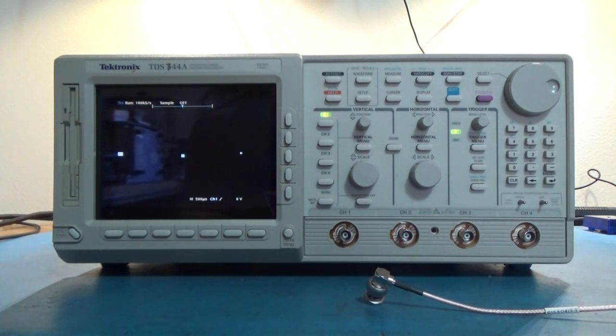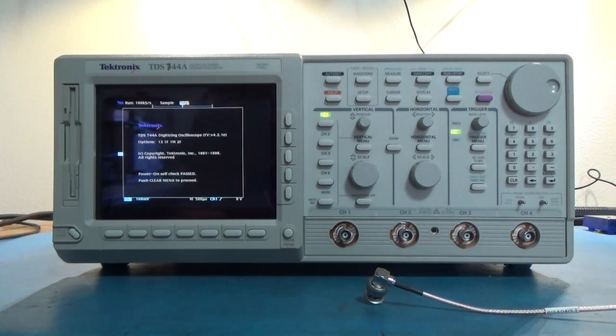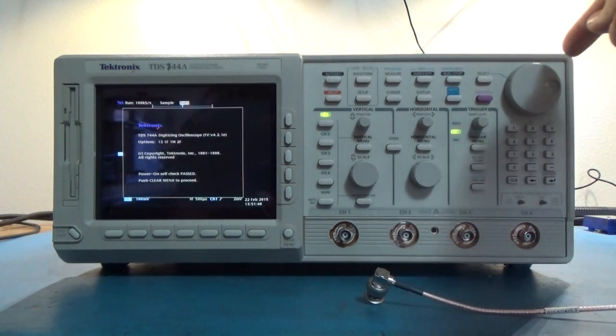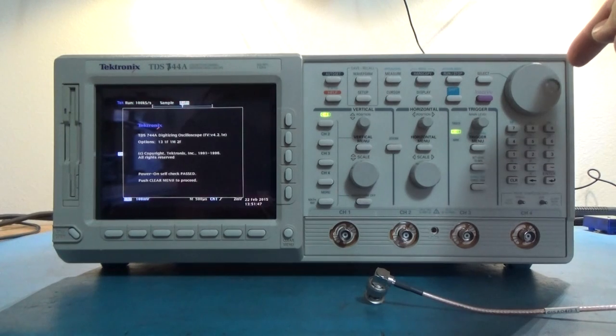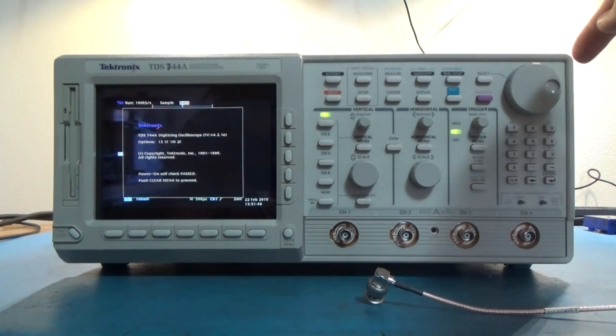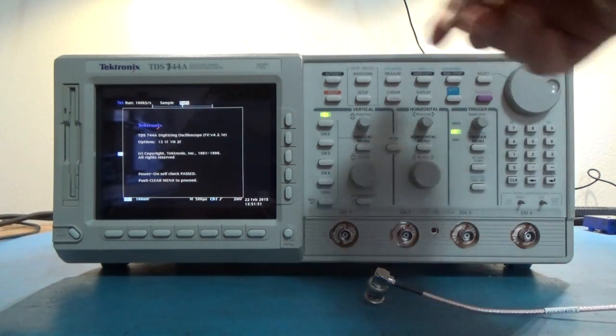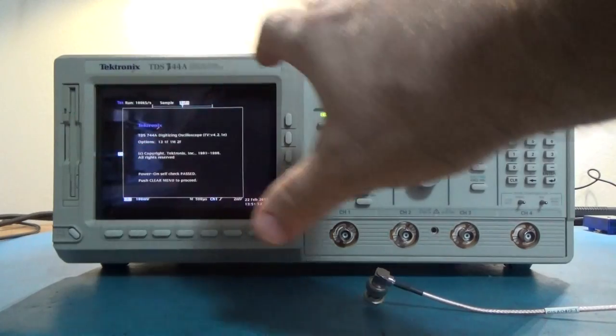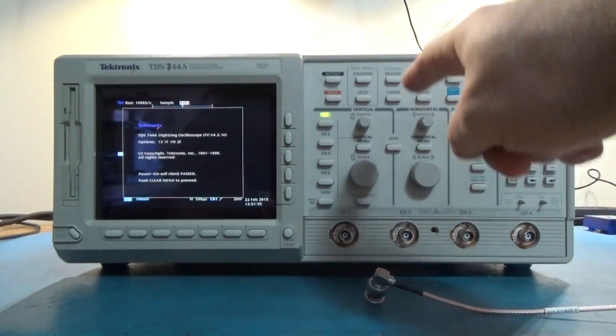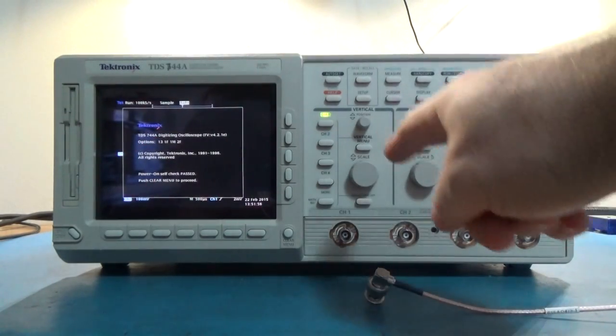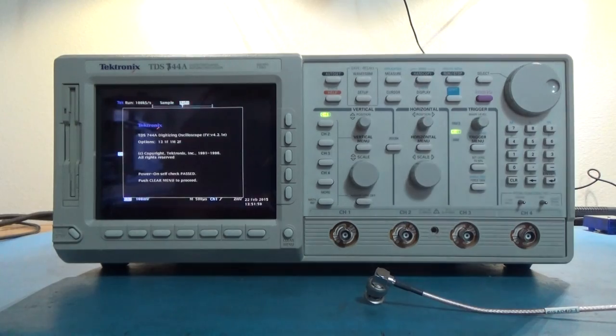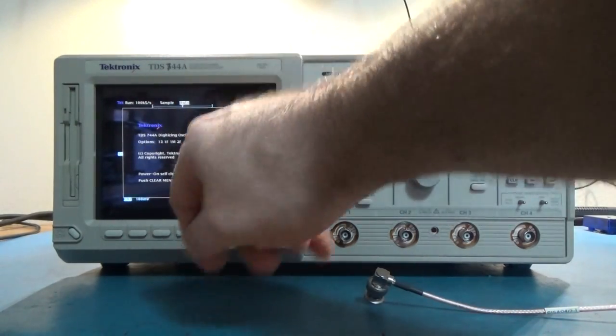This thing actually cost me $75. No one could get it to turn on and that's because someone had left the cal switch in the back, switched to the memory unprotected mode, which won't allow these to boot up. You can see that it's a 744A.